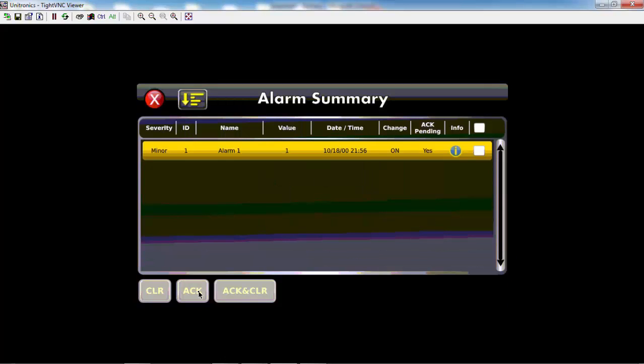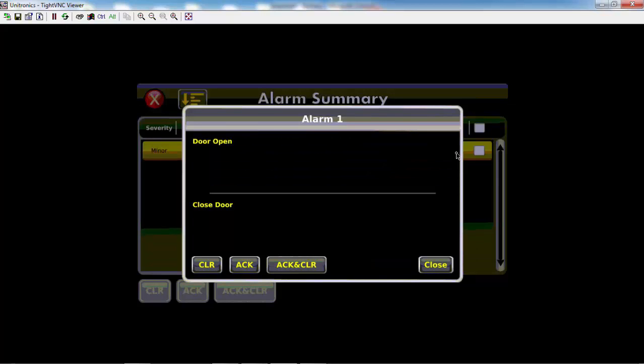The alarm summary list is automatically generated by the alarm system. This is a list showing the status of the alarms that are currently active in the alarm system and is a subset of the current alarm log. Press the info I icon of a specific alarm to view the alarm description and countermeasure instructions. Here, the user can also perform clear, acknowledge, as well as simultaneous acknowledge and clear actions.